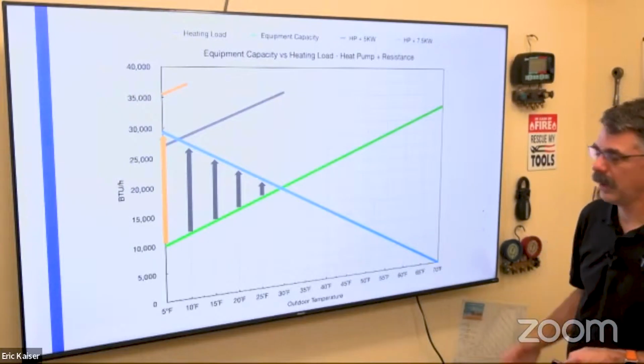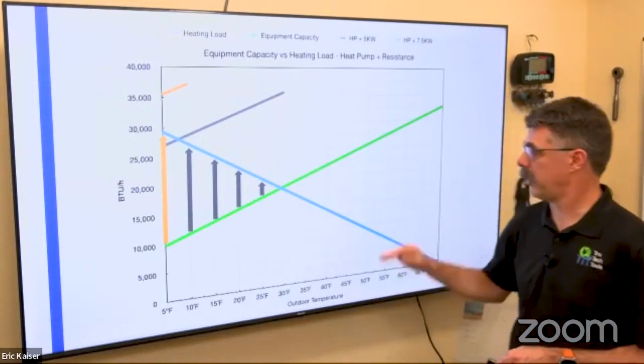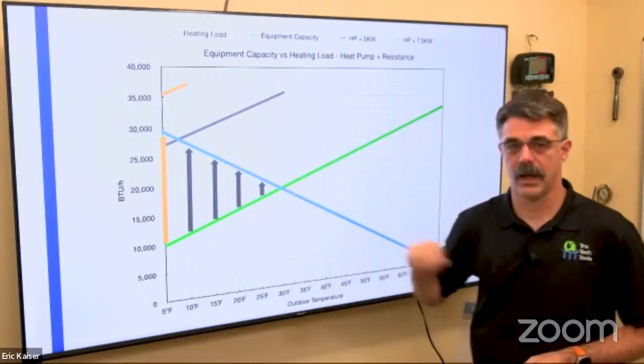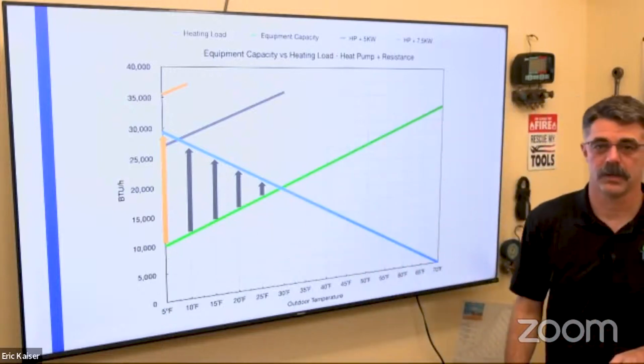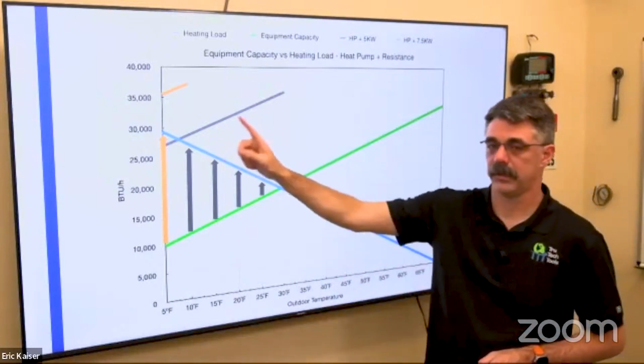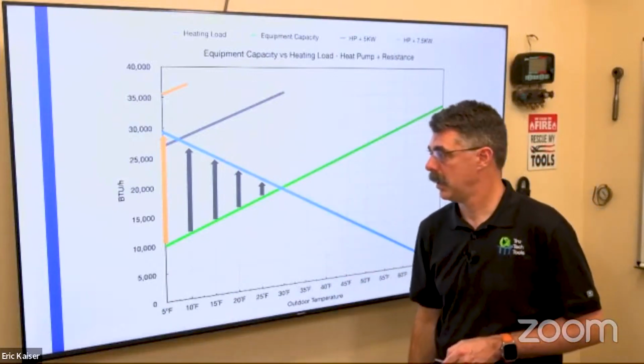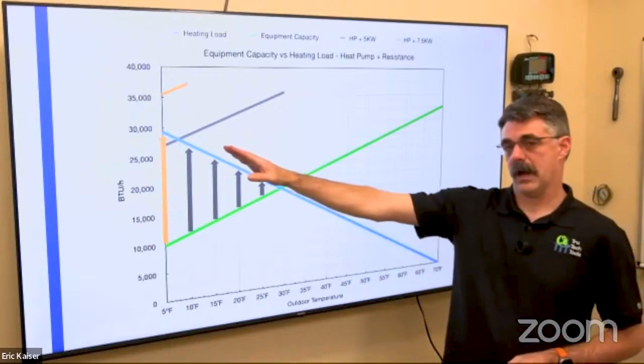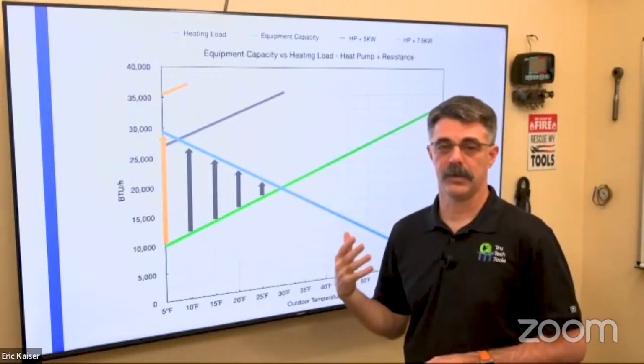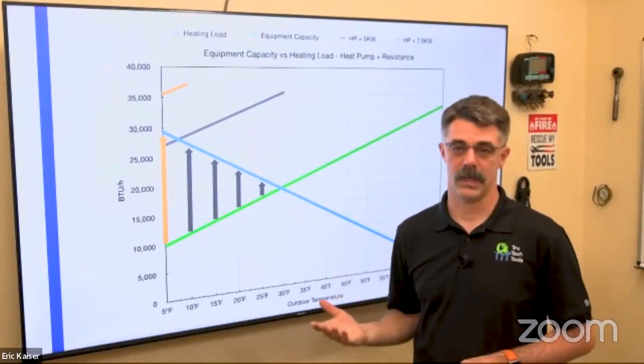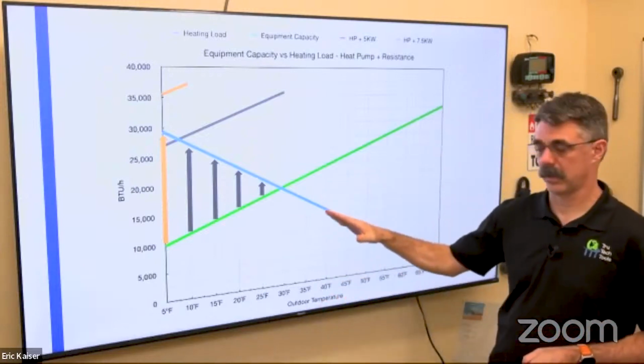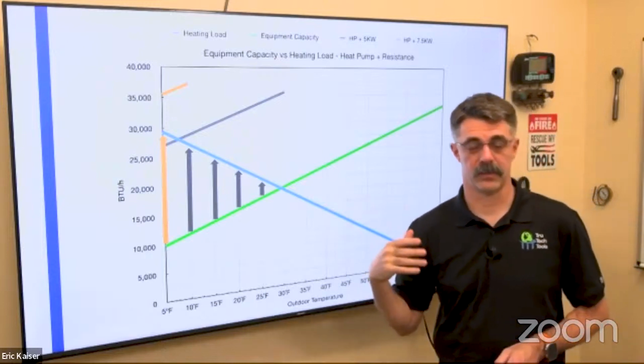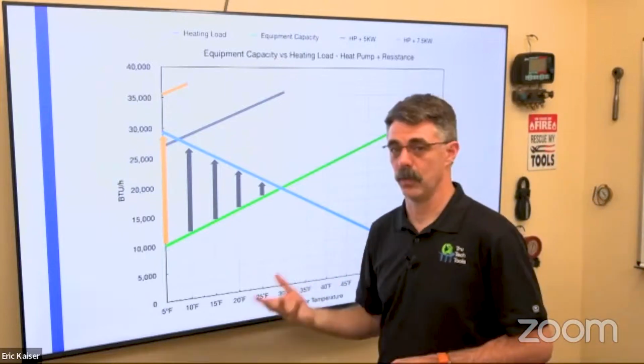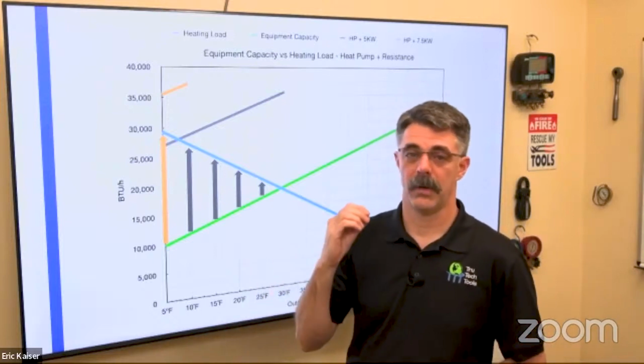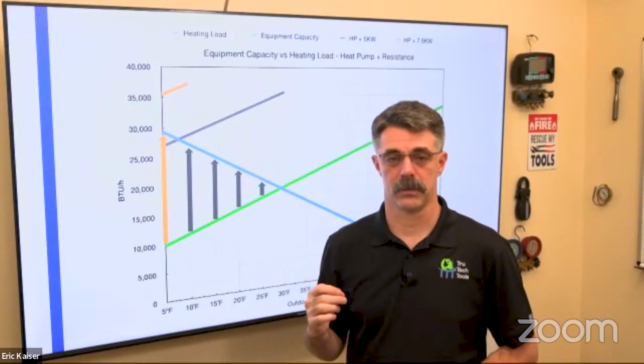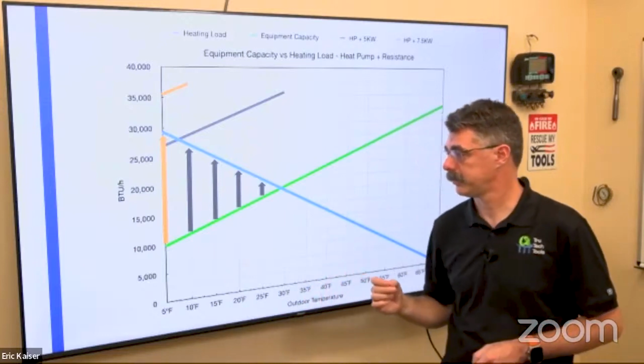Now, let's look at this a little differently. This is my performance line here, that green line again. We're back to our single stage heat pump plus some electric resistance heat. The blue line now, though, is the load slope of the house. This is how much heat the house needs. And this line's actually going to move a little bit depending on the conditions outside. Is it sunny? Is it not sunny? Is it windy? Is it not windy? It's not all about just outdoor dry bulb temperature. A lot of other factors go into it.